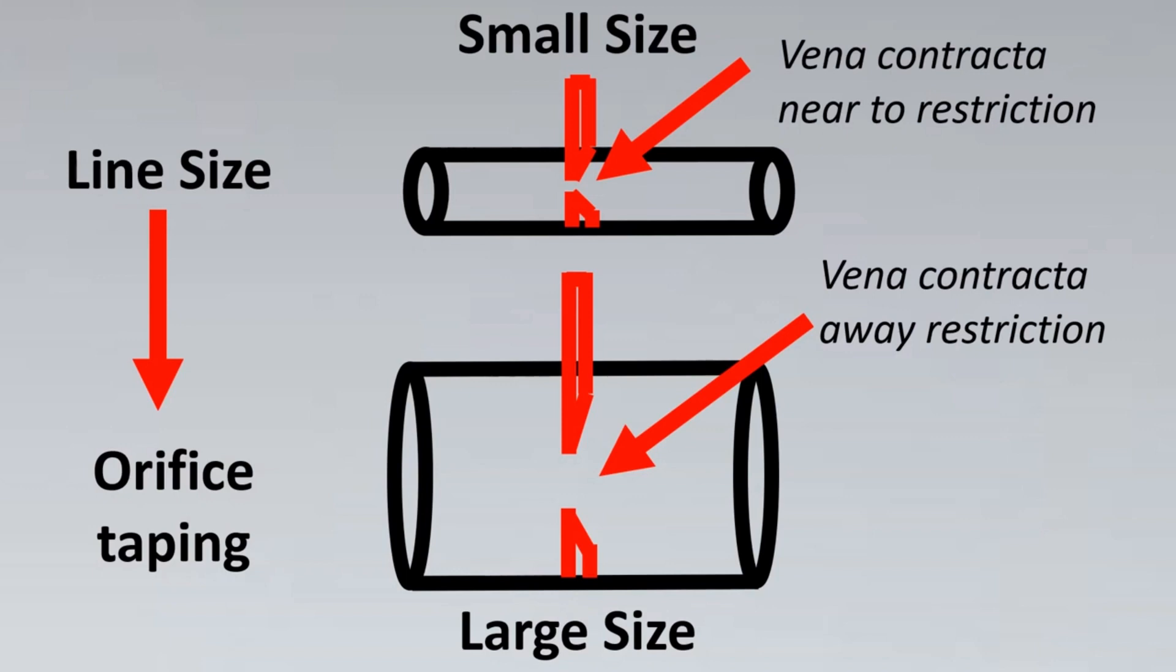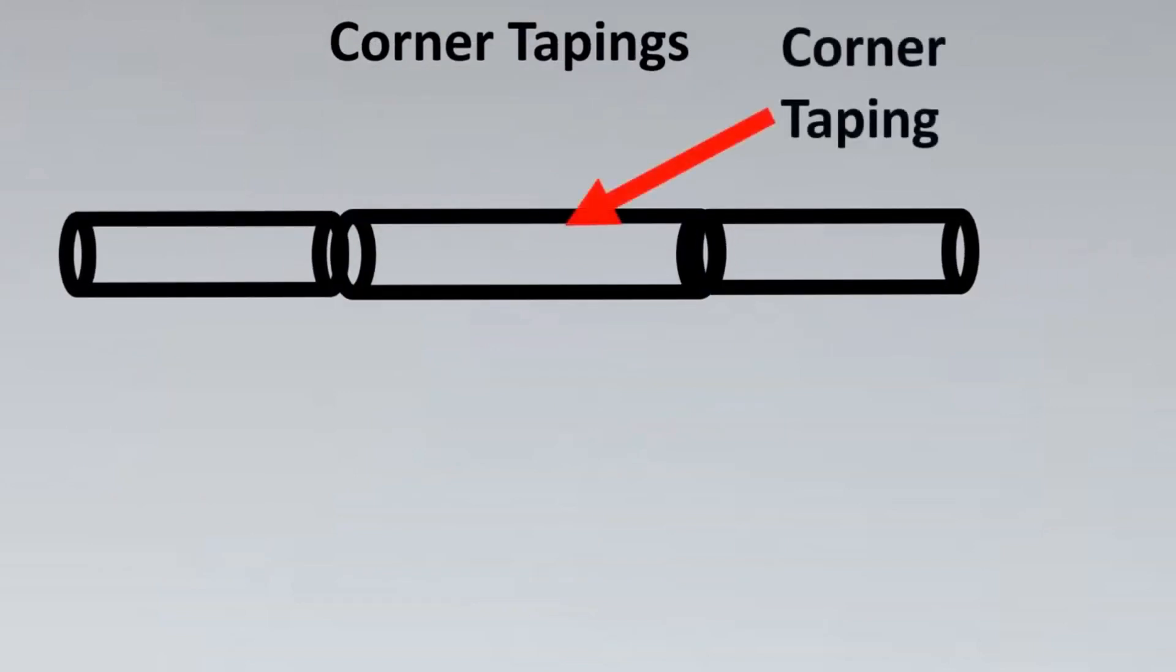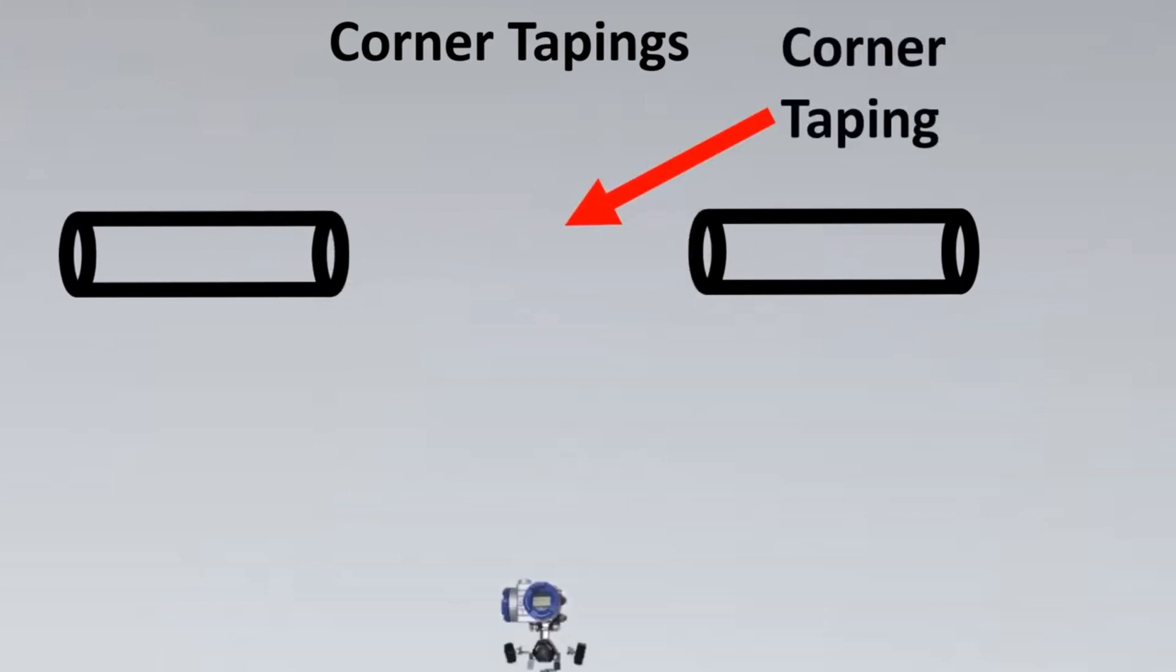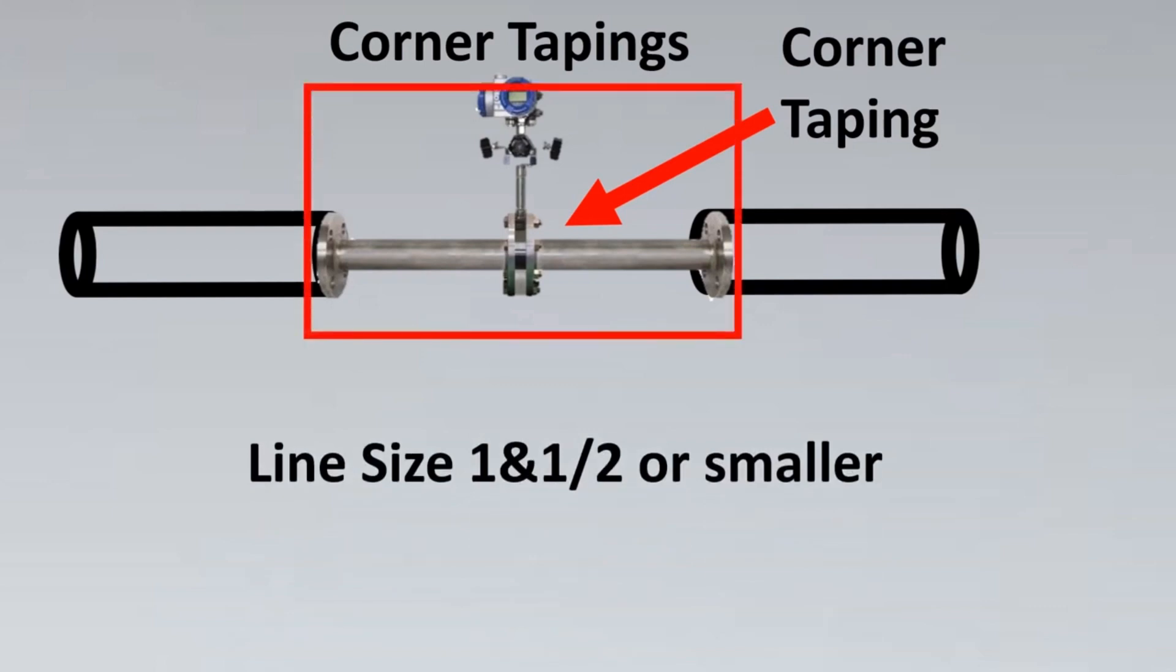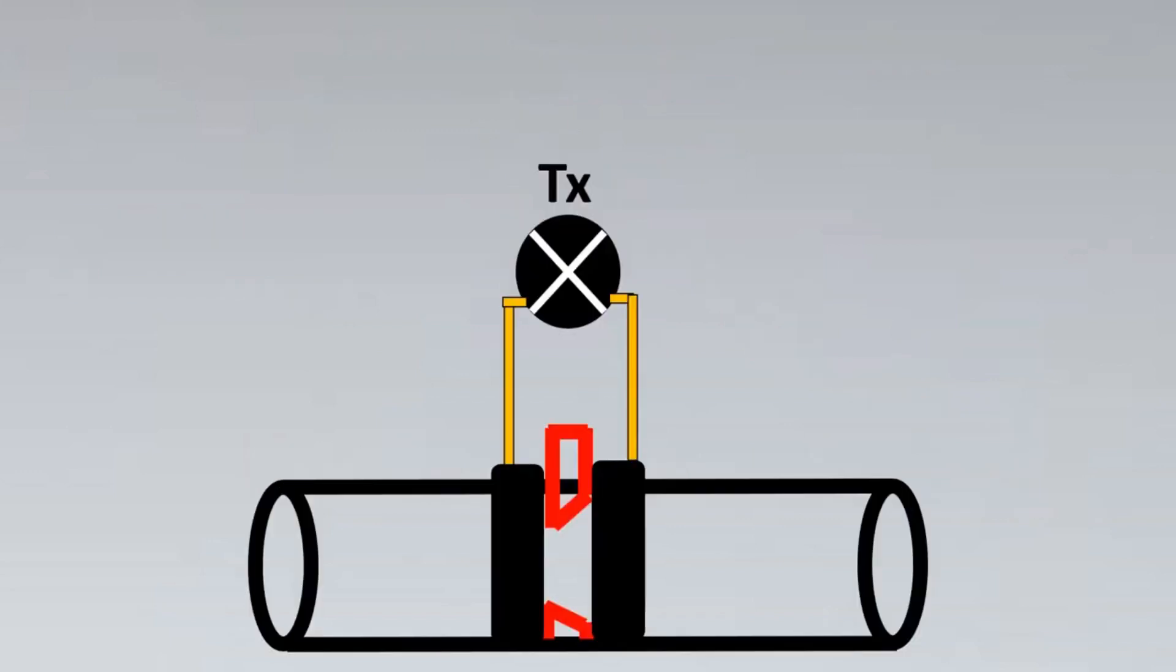For the first case, we will go for corner tappings. Imagine this is our piping assembly, and in this center we want an orifice with corner tappings because it is a small line size. Here we have an integral orifice assembly that is usually preferred for corner tappings. These corner tappings are usually preferred for line sizes which are 1.5 inch or smaller. This entire assembly is actually given to us by vendor, so we have to just mate the flanges which are at the end with our piping flanges in the system.